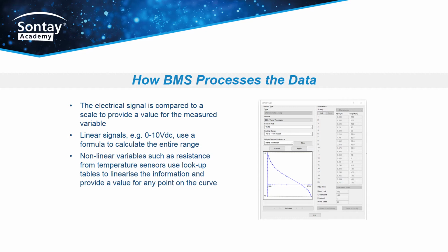Non-linear variables such as resistance from temperature sensors use lookup tables to linearize the information and provide a value for any point on the curve. For linear signals such as 0 to 10 volts DC, we simply need to take the voltage and multiply it by a factor, a coefficient, to ascertain the corresponding value.